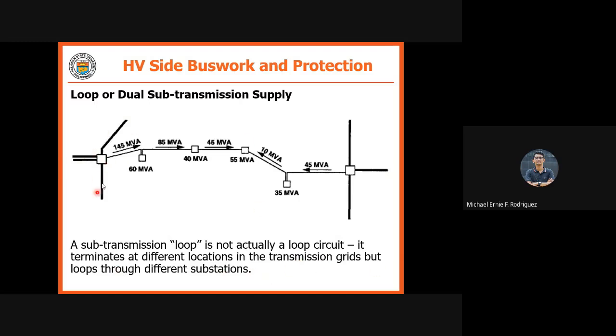So, from a transmission substation, okay, this is a transmission substation. Lumabas, we have 145 MVA. Okay. And then meron tayong mga substation rated 60 MVA, 40 MVA, 55 MVA, and 35 MVA. Nandito. So, 145 MVA minus 60 MVA. So, mag-flow na lang after this substation is 85 MVA. Then, after that, 40 MVA dito na substation. So, 45 MVA na lang mag-flow. And then, for the 55 MVA transformer, 45 lang natira. Plus, sa kabilang side, may natira pang 10 MVA. So, that is now 55 MVA.